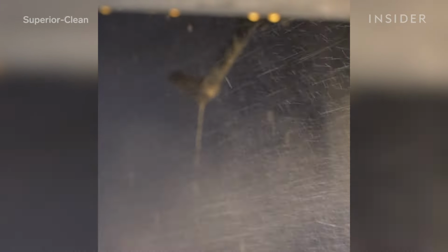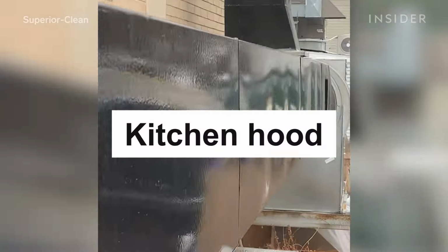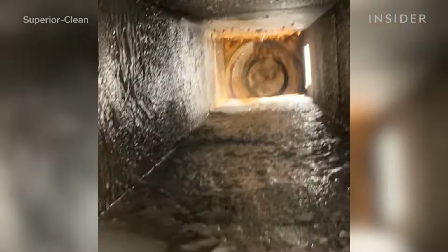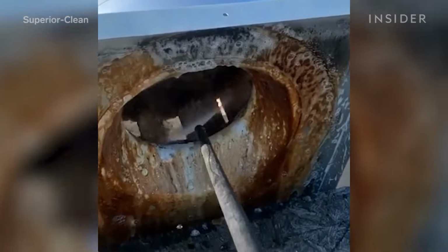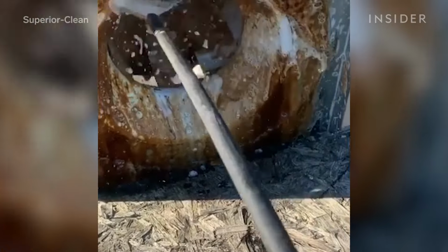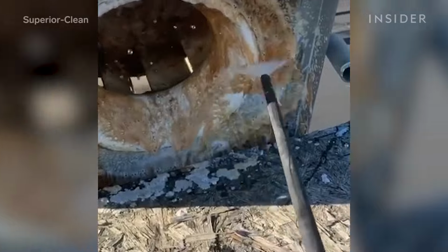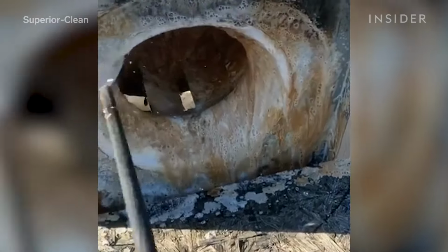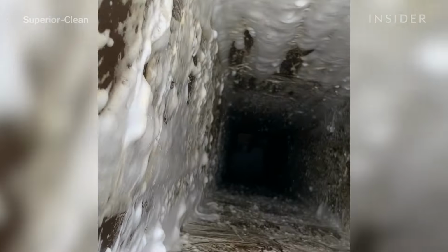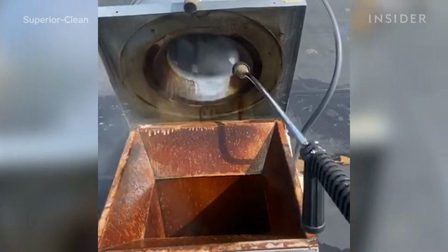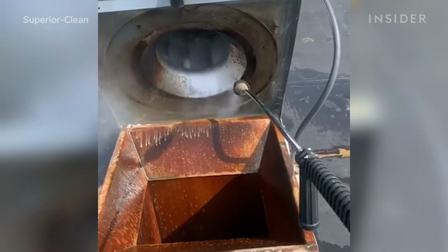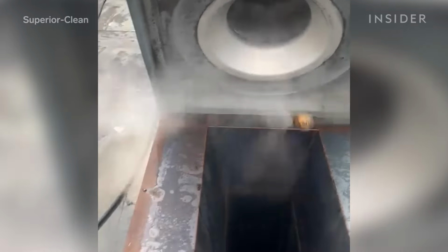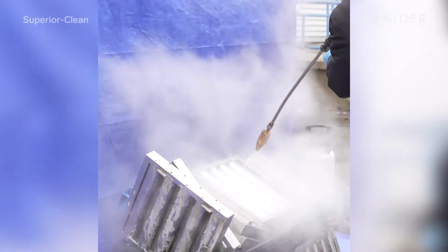We just finished off with steam cleaning the upper ductwork, which flushes the grease down through the inline exhaust fan. And now we're moving to the inner blades. So what we're looking for when applying the degreaser on the exhaust fan blades in the ductwork is the foam. Once you start to see that the grease is turning into a yellowish tint of the color and it's foaming, you know that you're able to hit it with the hot water pressure washer. The temperature of the hot water pressure washer allows the grease to really soften up, and it moves a lot easier than trying to do with a cold water pressure washer.